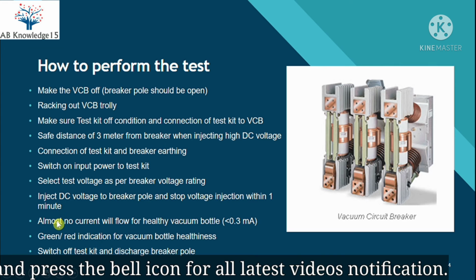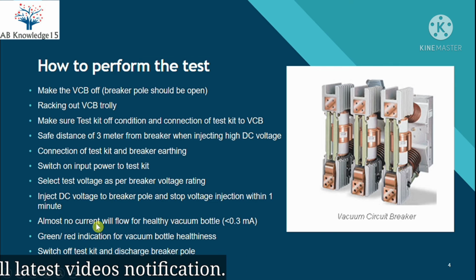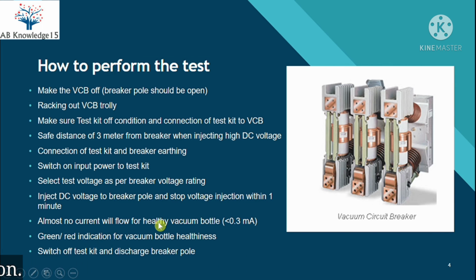Within the 1 minute, in some kits you will see a meter for voltage and current. For the healthy condition of the vacuum bottle, the current should be less than 0.3 milliamps. In some other types of test kits, green and red indications are provided for vacuum bottle healthiness. When the green or red indication shows, the voltage injection stops and you will know the condition of the vacuum bottle. Green shows the healthy condition of the bottle and red shows the faulted condition of the vacuum bottle.